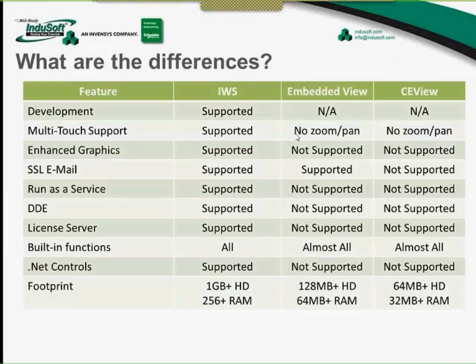Enhanced graphics. InduSoft Web Studio introduced the enhanced graphics. Recently we have improved that in version 7.1, applying anti-aliasing and things like that. Those features are not enabled for embedded view and CE view. And it makes sense when you think about it, because usually the applications with embedded view or CE view cannot require too much processing. So if we allow you to do heavy graphics on those devices, the user experience is usually not going to be very good. So that's why we also limit those capabilities.